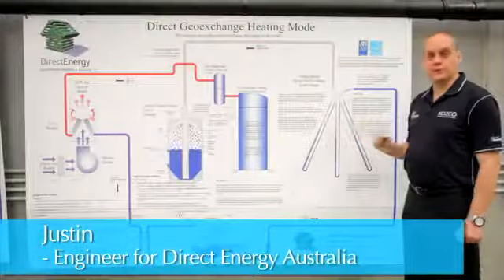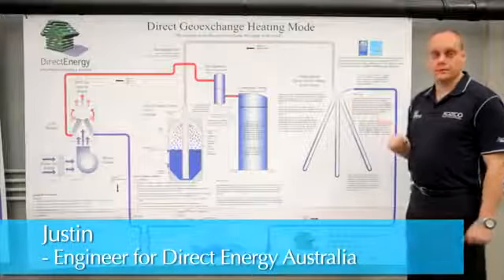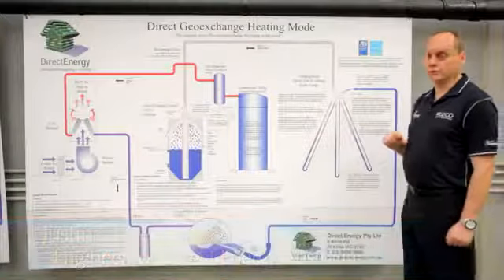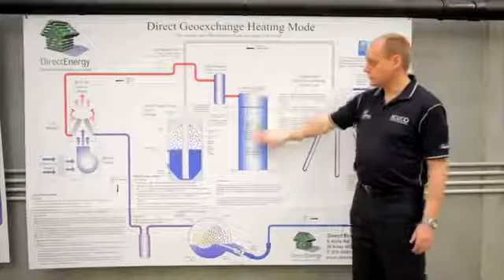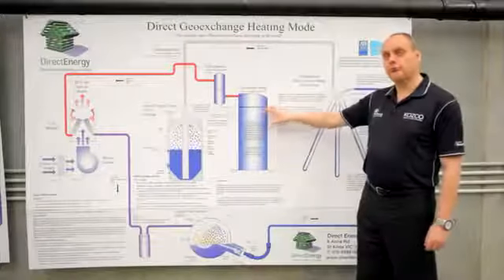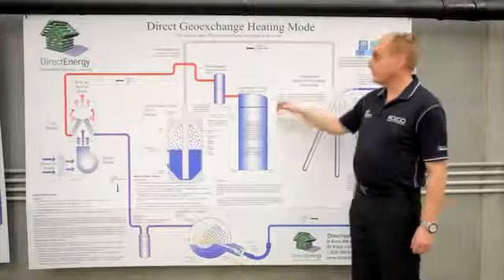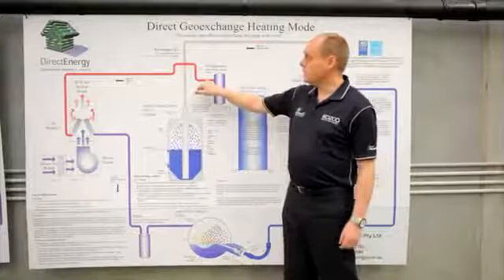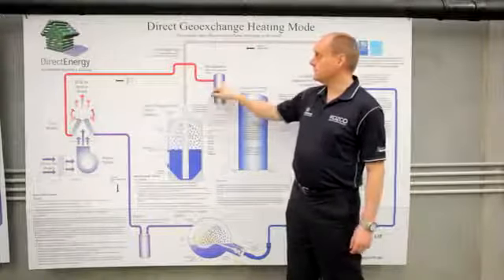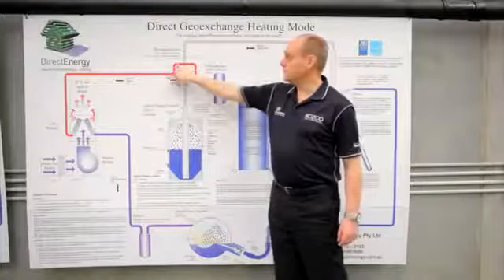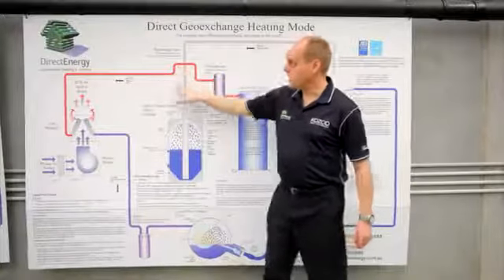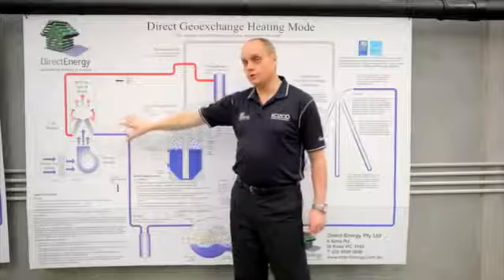This chart is demonstrating how the geothermal heat pump operates in heating mode, and I'll show you how it can be reversed to operate in cooling mode. In heating mode, the compressor is compressing the refrigerant and making it very hot. So it's coming off the compressor at quite a high temperature, in excess of 80 degrees Celsius.